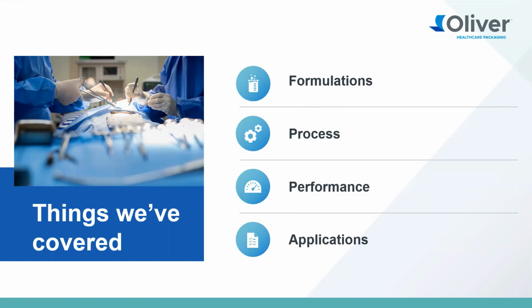Next, we talked about performance. Again, coatings provide us with a stable and uniform peel strength. It gives us, the end user, the adhesive transfer effect to visually inspect the integrity of the seal after it's opened. And it will also fight against other risks such as EO seal creep that we just discussed.